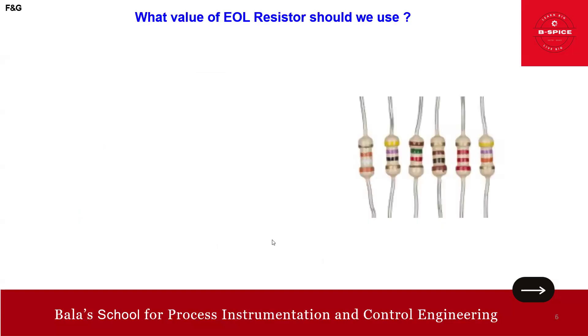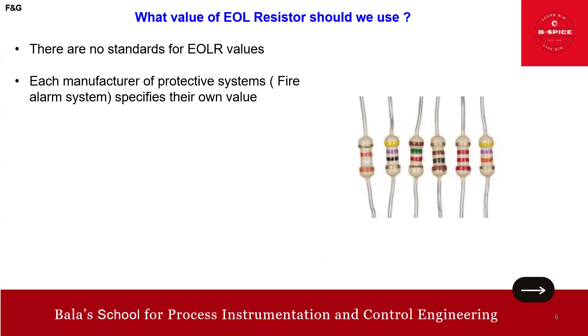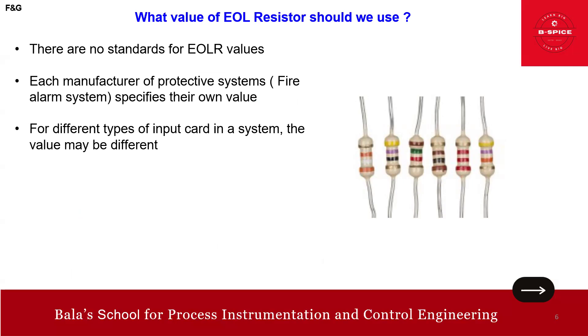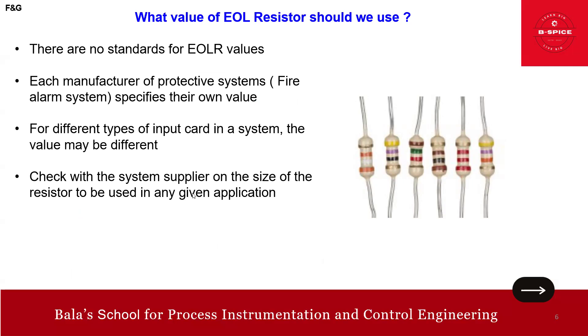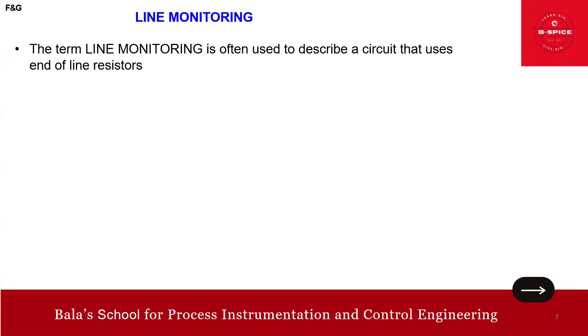Regarding the resistor value: there is no standard for EOLR values. Each manufacturer of a protective system, such as a fire alarm system, specifies their own value. For different types of input cards in a system the value may differ, so always check with the supplier for the correct size of resistor to be used in any given application.